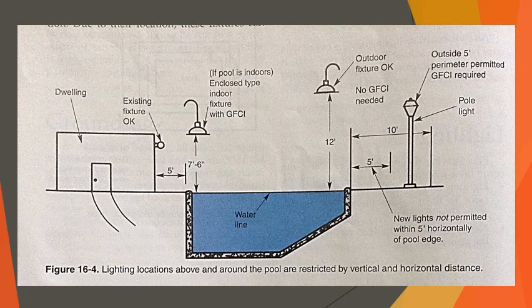Again, lights may also be installed above the pool and should not be installed less than 12 foot above the water line for outdoor pools and no less than 7 foot 6 inches above the water line for indoor pools. Indoor lights and fans above the pool must be GFCI protected and totally enclosed. The basic requirements for pool side and above pool lighting are illustrated in figure 16-4. Refer to sections 680.8 and 680.22.